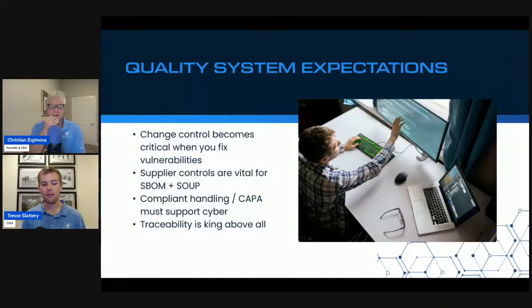Now, it's especially important when we're looking at a vulnerability that's come up in the system. We're assuming this vulnerability has some input, it's been discovered through testing, discovered through a risk analysis or a threat modeling exercise, whatever it might be. But we identified that there is a risk in the system. We had to make some change to remove that risk. We need to have all of this clean traceability going through from the identification all the way down to the verification that the risk remediation was sufficient.